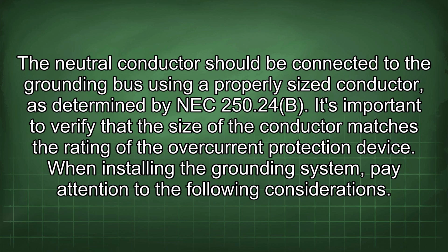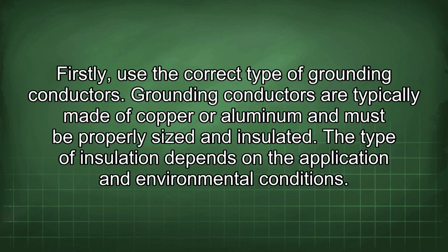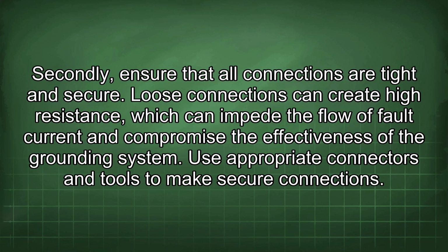When installing the grounding system, pay attention to the following considerations. Firstly, use the correct type of grounding conductors. Grounding conductors are typically made of copper or aluminum and must be properly sized and insulated. The type of insulation depends on the application and environmental conditions. Secondly, ensure that all connections are tight and secure. Loose connections can create high resistance, which can impede the flow of fault current and compromise the effectiveness of the grounding system. Use appropriate connectors and tools to make secure connections.